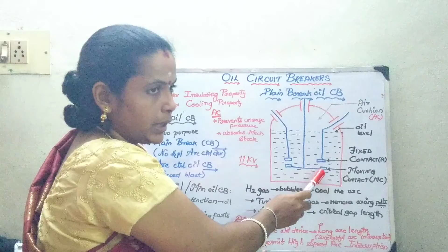Moving on to the construction, it consists of a dome shaped vessel, an airtight container, in which a part is filled with oil and there is an air cushion above. In this you have two breaks, that is two fixed contacts and two moving contacts. Since you have two fixed and two moving contacts and the breaks are applied in series, it is also called a double break or double plain break circuit breaker. A portion is filled with oil and there is an air cushion above.